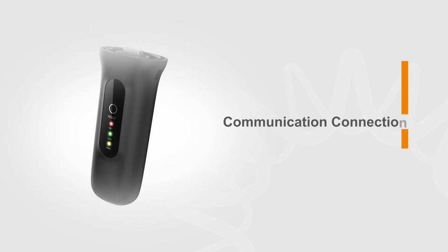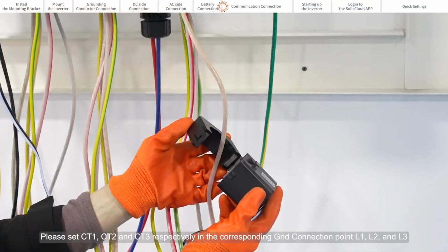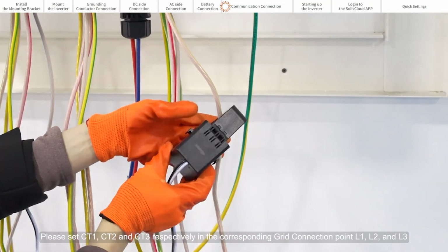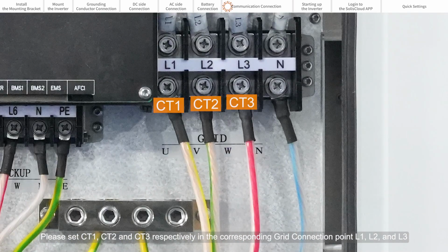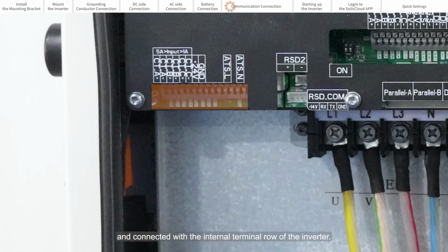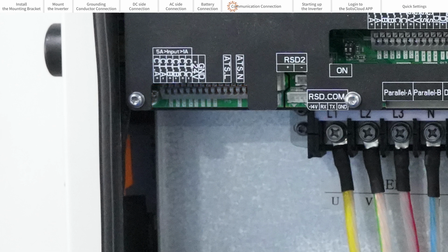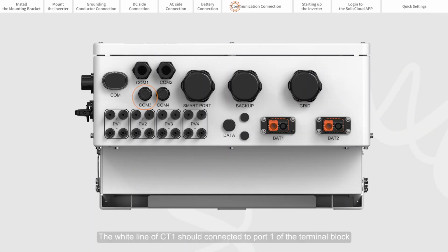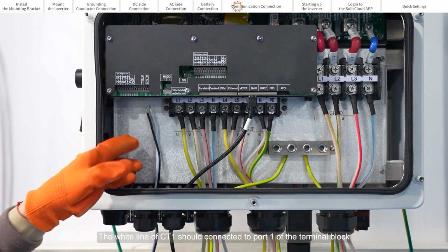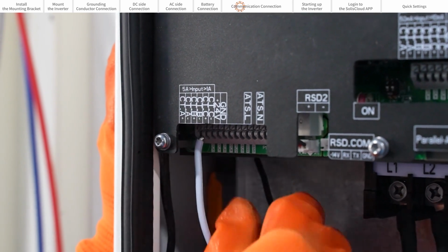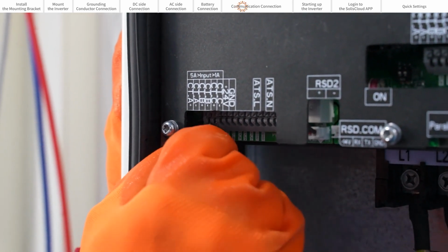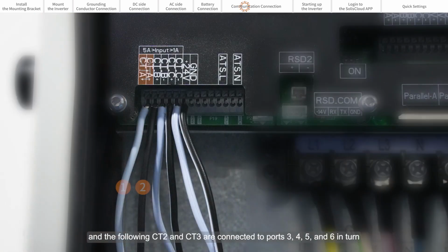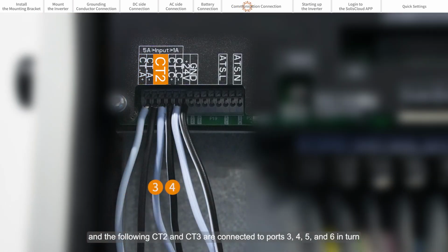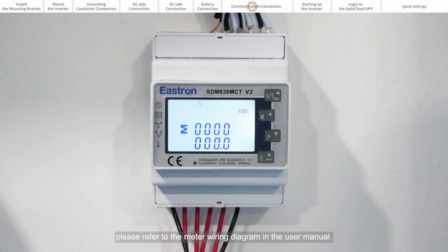Communication connection. Please set CT1, CT2 and CT3 respectively in the corresponding grid connection point L1, L2, and L3 and connect them with the internal terminal row of the inverter. The white line of CT1 should be connected to port 1 of the terminal block, the black line connected to port 2 of the terminal block. And the following CT2 and CT3 are connected to ports 3, 4, 5, and 6 in turn. If you want to install the meter, please refer to the meter wiring diagram in the user manual.